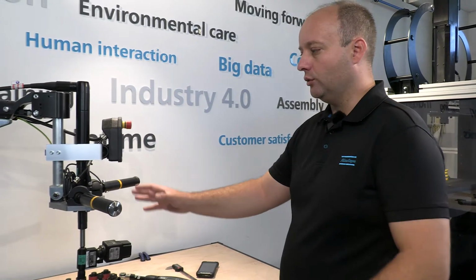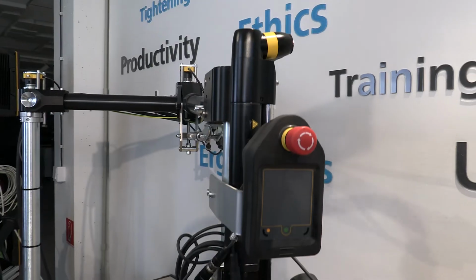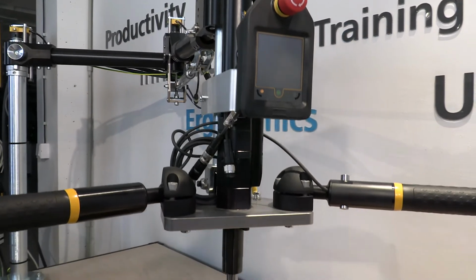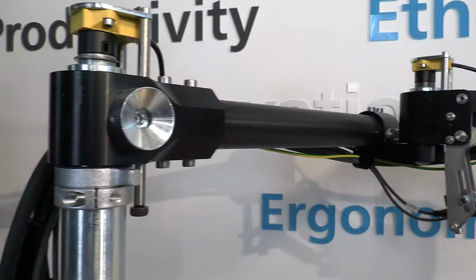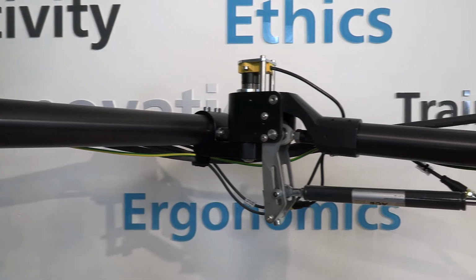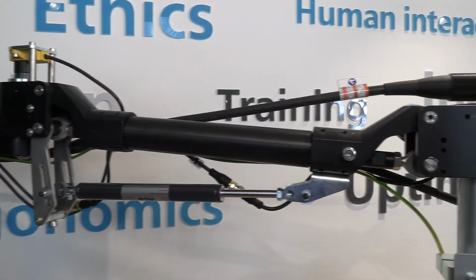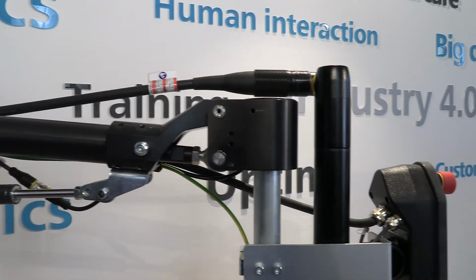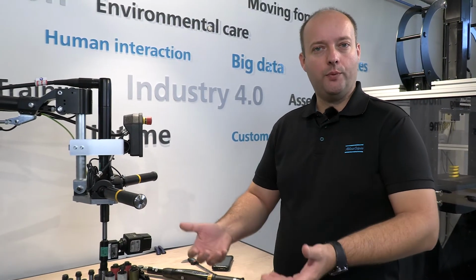Another advantage of this system, being wireless, is the ability to control fixed stations like this one. It saves time, especially since you don't have to disassemble the system - you can measure it this way. Or let's say you have a robot station with limited access, where you cannot be present while it's operating. Installing a transducer like this, getting out of the protected area, and running the test is a simple task.